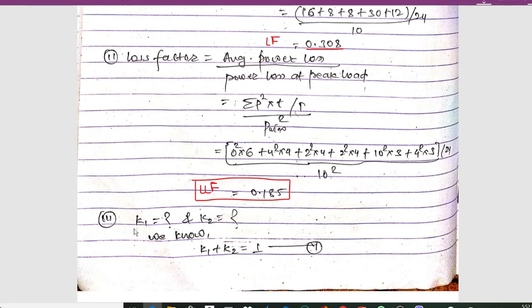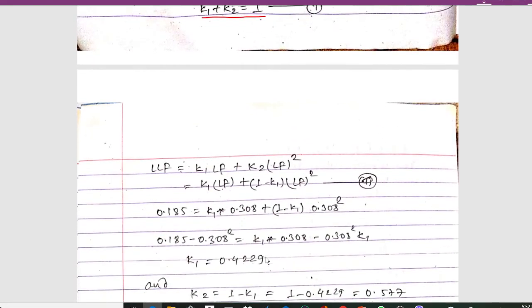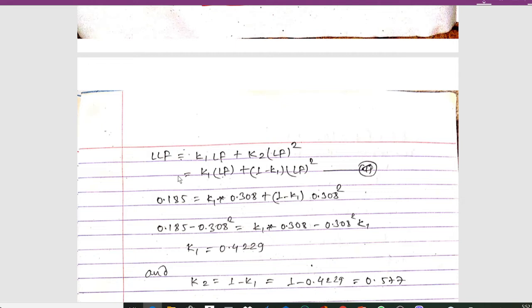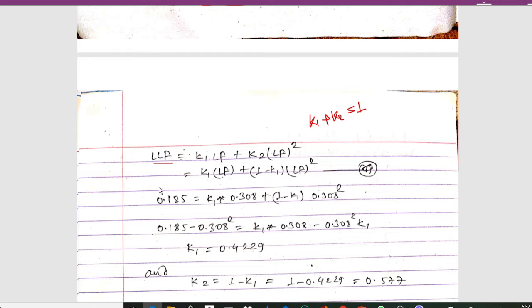Now we have to determine constants k1 and k2. We know the equation k1 + k2 = 1. We also have the relation: loss factor = k1 × load factor + k2 × load factor². Since k1 + k2 = 1, we get k2 = 1 - k1. Substituting into the loss factor equation: 0.185 = k1 × 0.308 + (1 - k1) × 0.308².